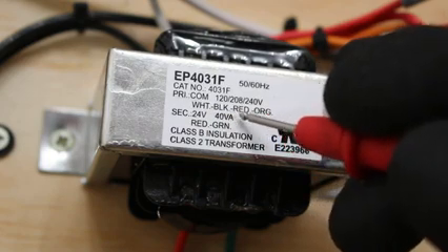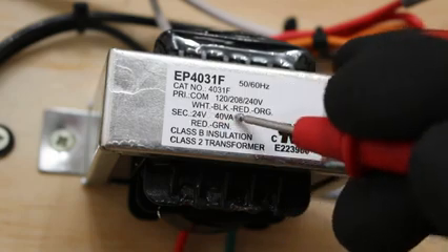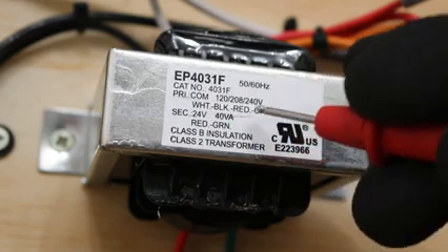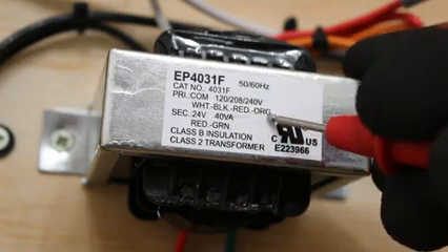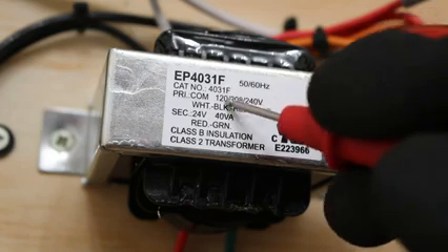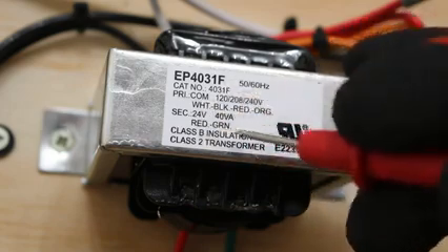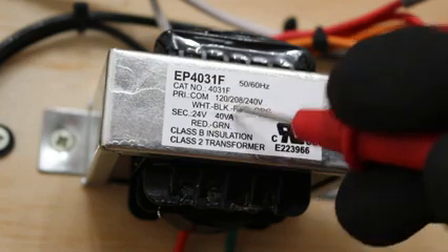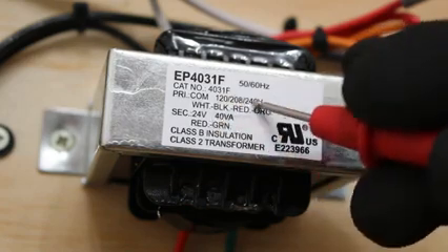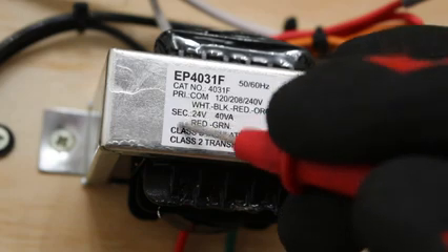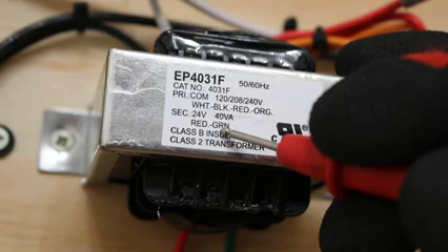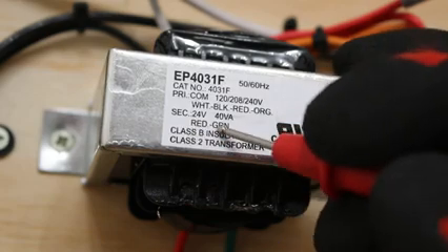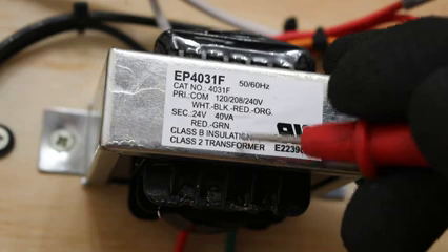If we had 208 volts, you're going to notice the white and red is connected. If we had 240 volts, we're going to notice the white and the orange is connected. From there, we have a secondary coil where we're going to step down the voltage from either 120 to 24, 208 to 24, or 240 to 24. So your secondary is red and green. All right? So those are the colors of our wires. Those cannot be changed. It is what it is.